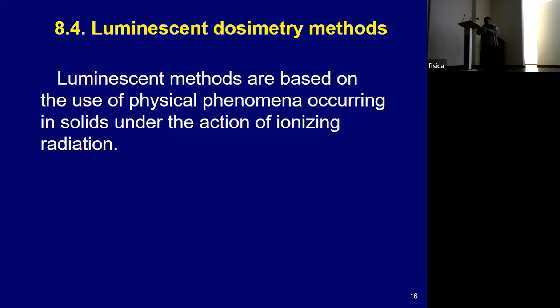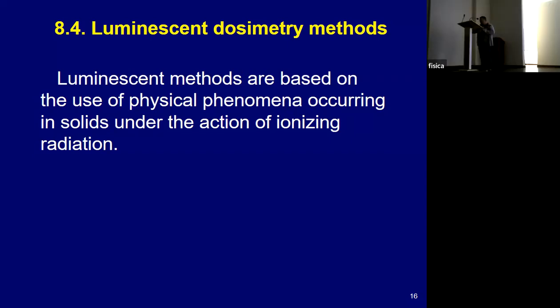Thermoluminescent methods. The essence of this method lies in the fact that charge carriers, electrons and holes formed in the phosphor under the action of ionizing radiation, are localized in capture centers, as a result of which the absorbed energy is accumulated, which can then be released upon additional excitation. That additional excitation can be caused either by heating or by illuminating the phosphor with a certain part of the light spectrum. The optical effects observed in this case can serve as a measure of the absorbed dose.